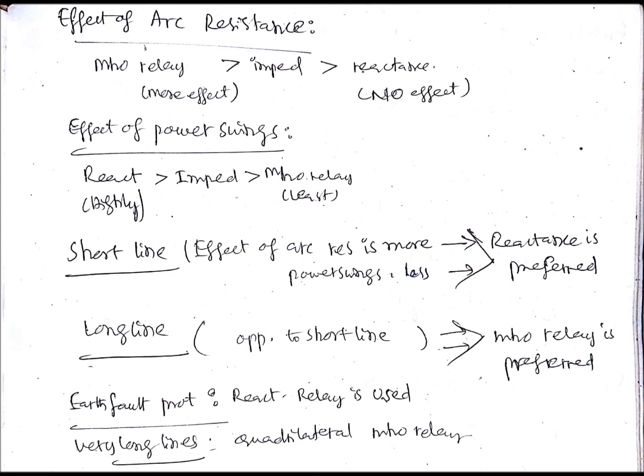Which type of distance relay will be preferred in case of arc resistance? For a short line, the resistance is more significant — we cannot neglect the resistance value. The resistance of a short line is comparable to the reactance, so arc resistance included in the measurement could cause faulty operation of the relay. Therefore, in the case of a short line, we need to use a relay which has very little or no effect due to arc resistance, which is the reactance relay.